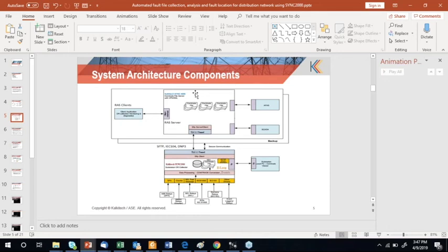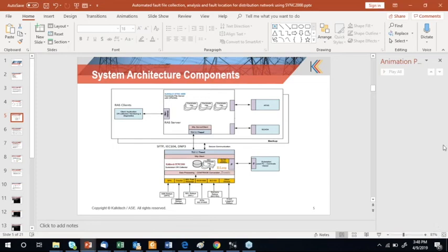and in the central system doing the detailed analysis. So based upon their analysis, if a single fault occurred in a substation, it completely recovers the cost of their installation. That is the ROI calculation they came across, based upon the 150 installations in multiple EDP substations. How they went about it is, first they implemented in 5 substations as a pilot. They tested the complete use case scenario, and once they were satisfied, they worked out the further deployment, and it is deployed across 150 substations.